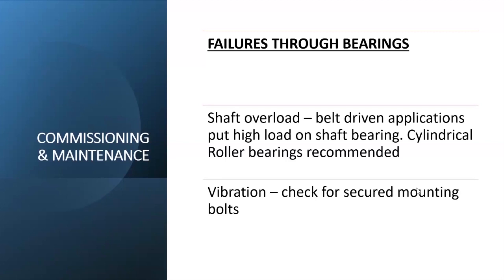Vibrations are found to cause a lot of motor bearing failure. So we do not leave vibration checks to only the mechanics or the condition monitoring technicians. As professionals, we ensure that there are no vibrations, because where there are vibrations, we are reducing the lifespan of the motor bearing.